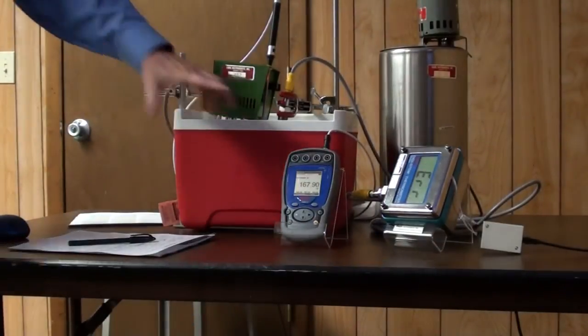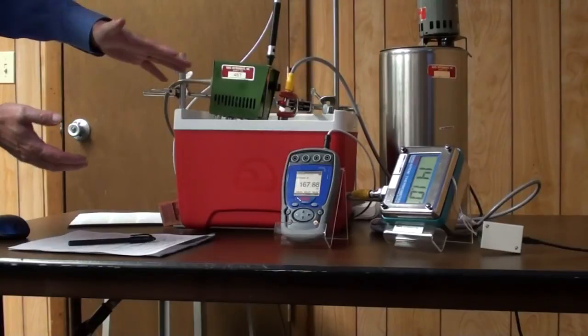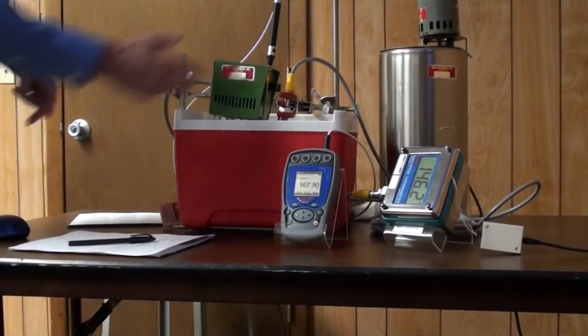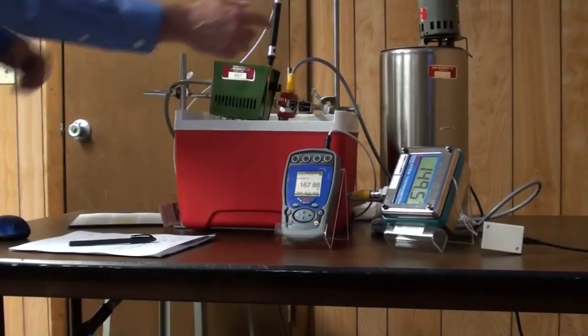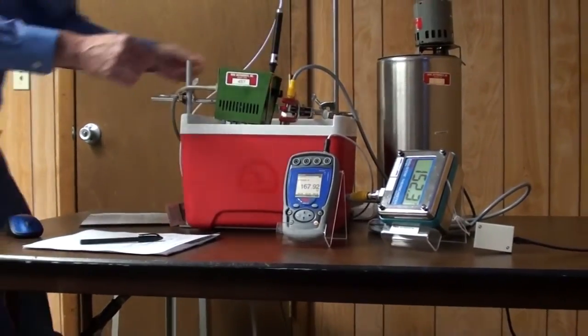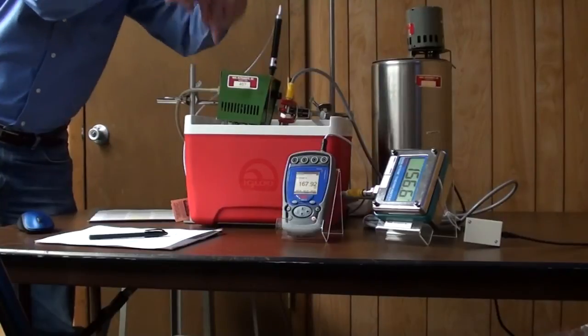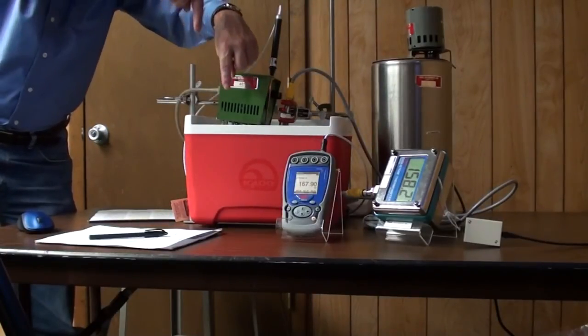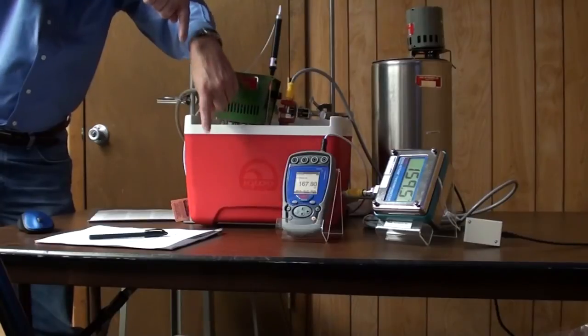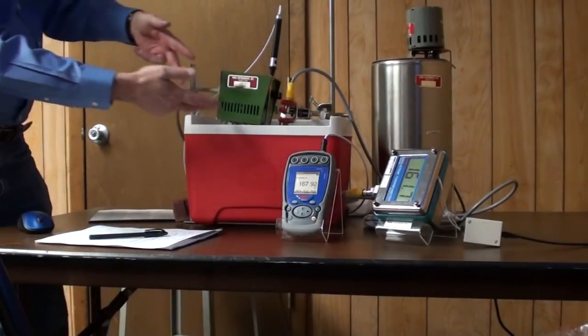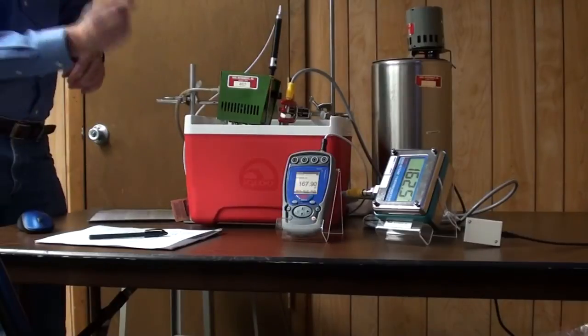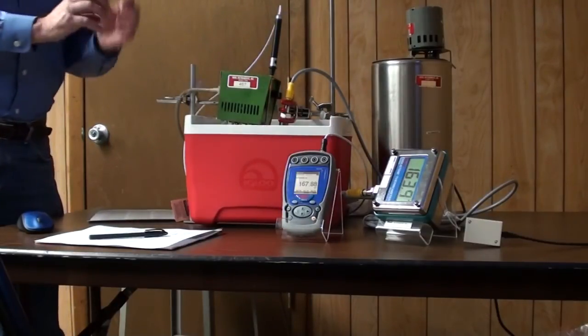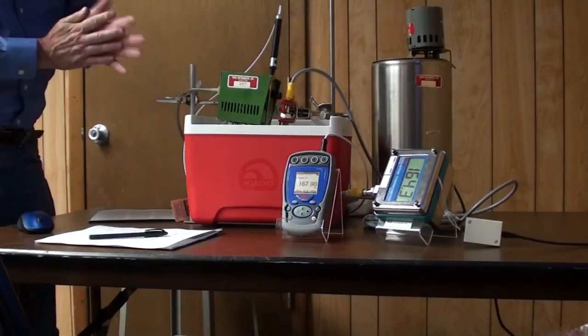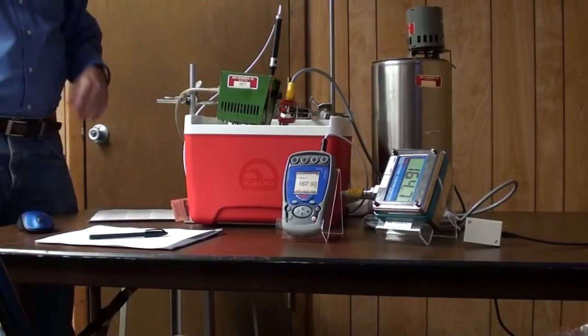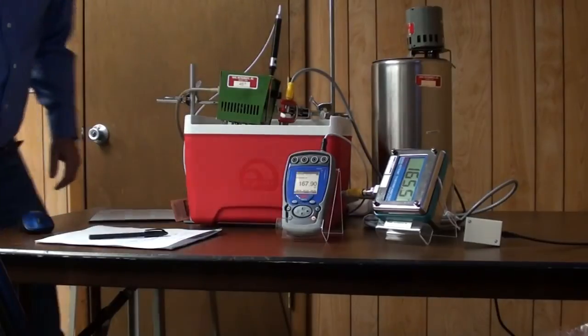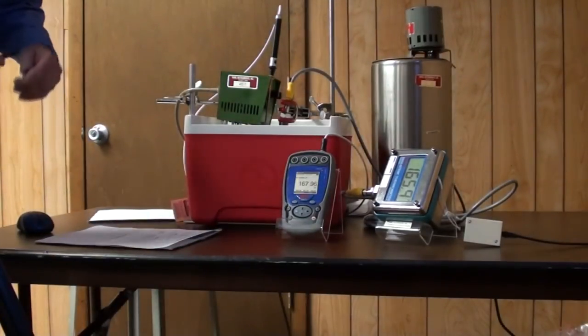We want to make sure we have 4 inches of immersion on it. We want to make sure that we're close to our standard instrument, and when you're doing calibrations, make sure that both these probes are about the same depth. You don't want your standard instrument up here and the probe you're calibrating down here. And remember that the sensing element in these devices is the bottom half inch, where that sensor is located. So that's really the critical part of that. We're still coming up on that.